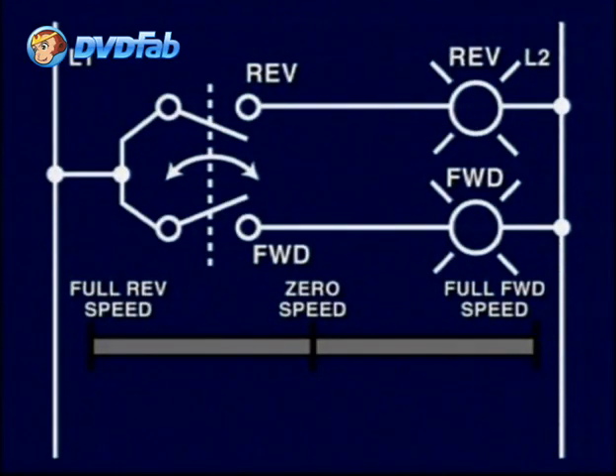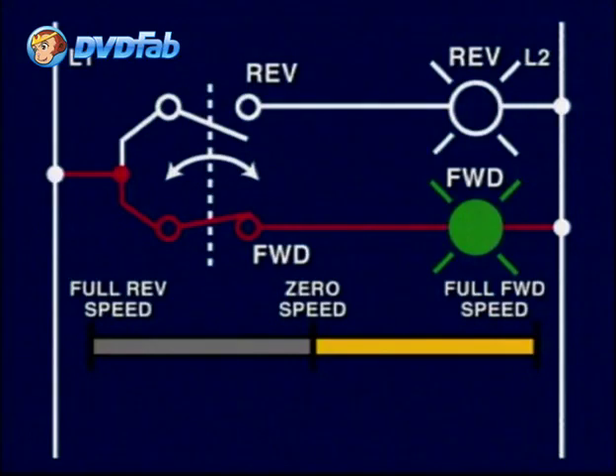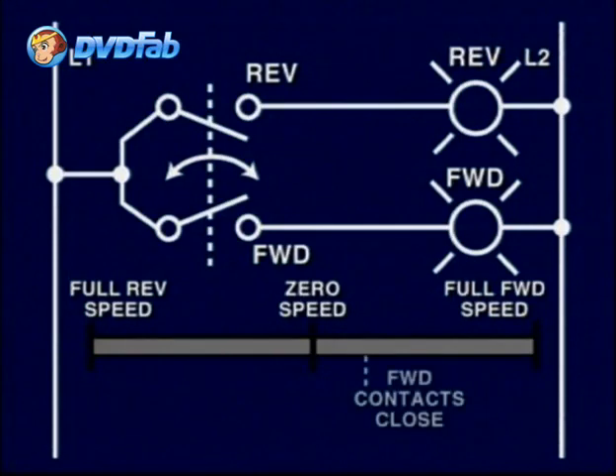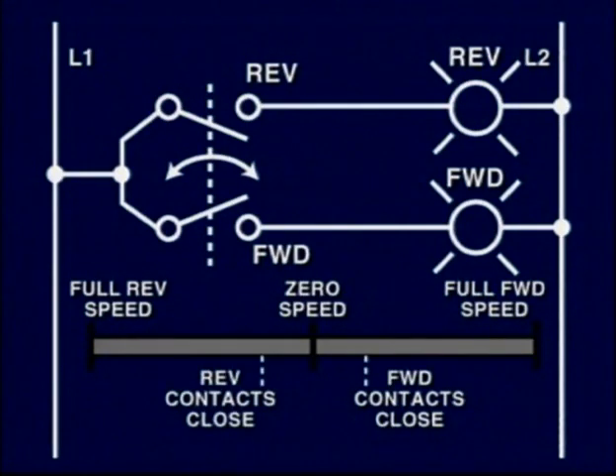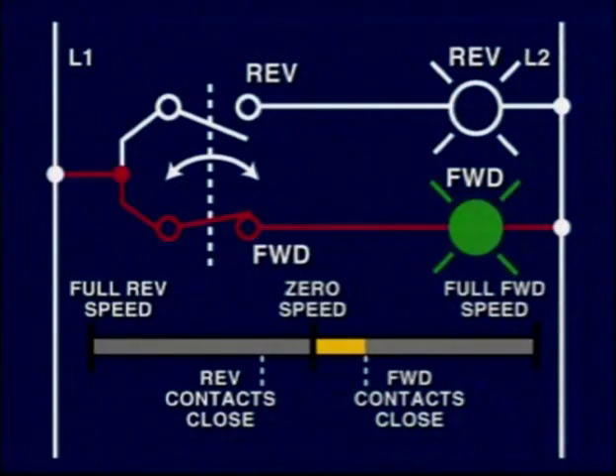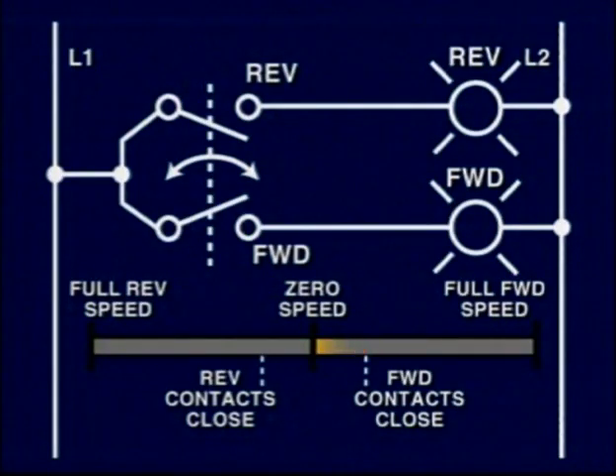If we have a plugging switch attached to the shaft of a motor, the centrifugal force created by the rotation of the shaft will cause the forward set of contacts to close once the motor starts to go forward. The speed, or RPMs, at which the switch will close is adjustable. Let us assume that the contacts close in the forward motion around here and in reverse around here. In between this area, the switch contacts will be open. Once the motor starts and passes this speed, the forward contacts will close. If the motor is stopped, the switch contacts will be off after the motor is slowed down at this trigger speed.